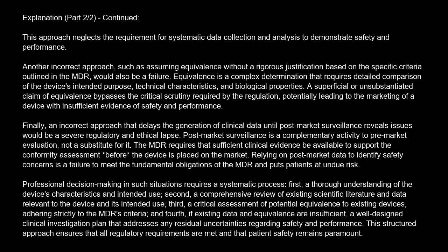Finally, an incorrect approach that delays the generation of clinical data until post-market surveillance reveals issues would be a severe regulatory and ethical lapse. Post-market surveillance is a complementary activity to pre-market evaluation, not a substitute for it. The MDR requires that sufficient clinical evidence be available to support the conformity assessment before the device is placed on the market. Relying on post-market data to identify safety concerns is a failure to meet the fundamental obligations of the MDR and puts patients at undue risk.